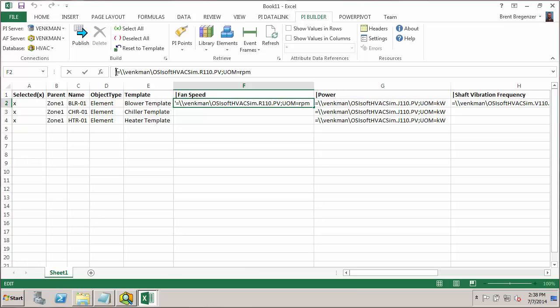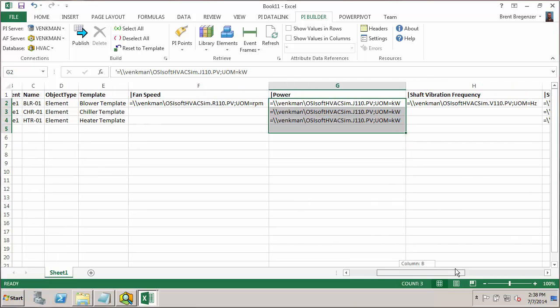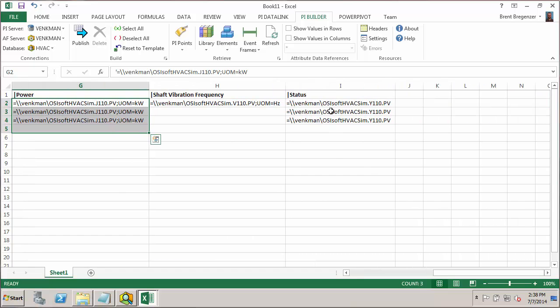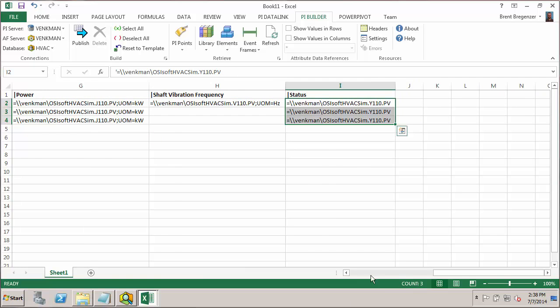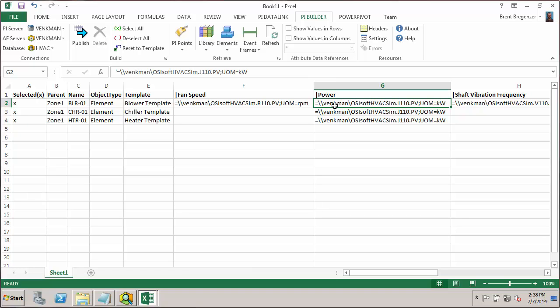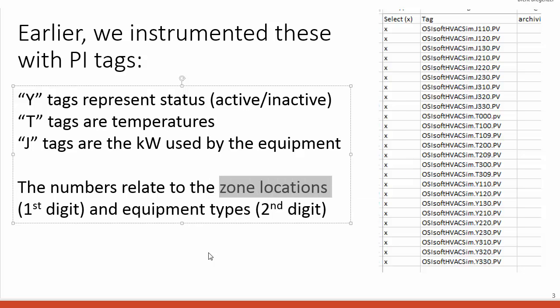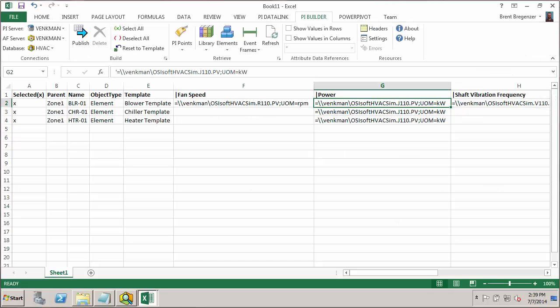Now before we move on to building our Zone 2 and Zone 3 elements, I want to make sure everything is okay with the Zone 1 elements. And you can see here that these power tags are all the same for all three pieces of equipment and the same for the status. And that's because when we built that base equipment template, just as a quick and easy way to finish that process, we selected the tag for the Zone 1 blower. But in reality, if you remember from our tag naming convention, if I jump back to our HVAC system presentation, we saw that there's this code here and that each of the letters in the code indicate what type of tag is being used. And the three-digit numerical code, the first digit is going to indicate our zone locations, and the second digit is going to indicate our equipment type. So here these are all zone 1 equipments. So the first digit is fine. It's a 1. But we need to update the second digit for the chiller and the heater.